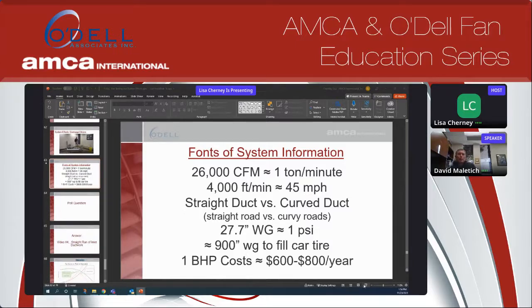At 4,000 feet per minute, the air is moving about 45 miles per hour. So if you think about that pickup truck going through a piece of ductwork every 3 minutes, the straighter the ductwork is, the more efficient it's going to be. If you have abrupt T's or very tight radius elbows, it's like driving a car or a truck down a tight, twisty road. You're not going to get there as efficiently as if you have a nice straight road. And I think the reason you see a lot of system effects is that people think air, being 0.075 pounds, is super light, so they're not moving much mass. The reality is that you're moving a lot of mass through a fan at a relatively high speed, and you have a lot of losses associated with it.